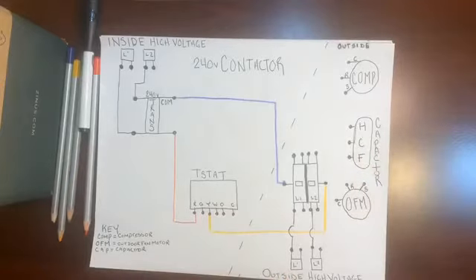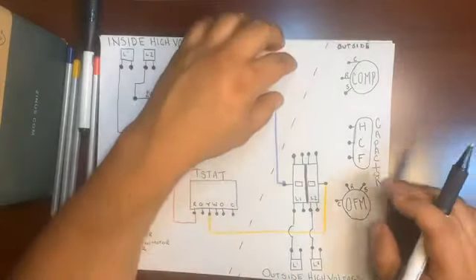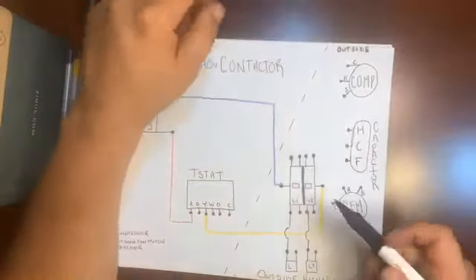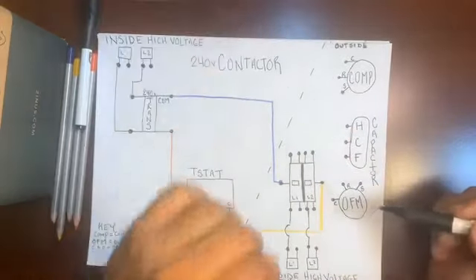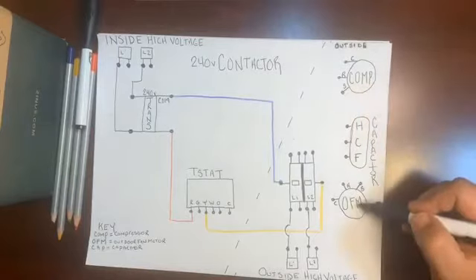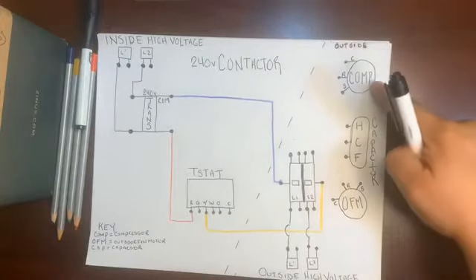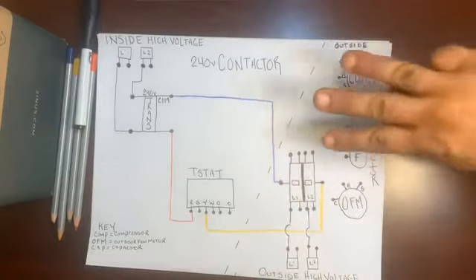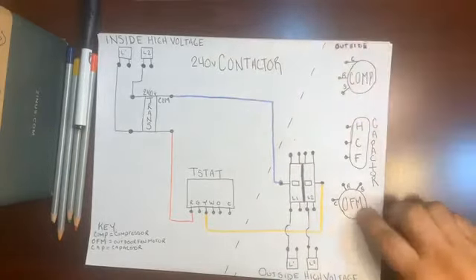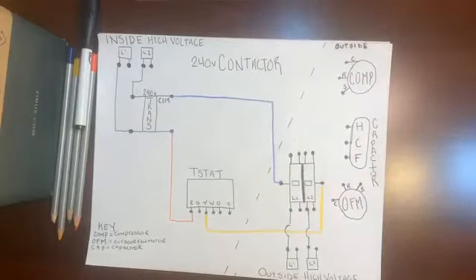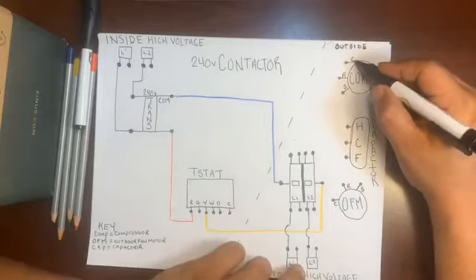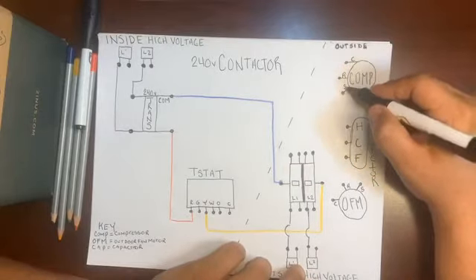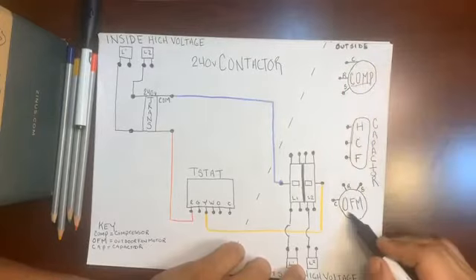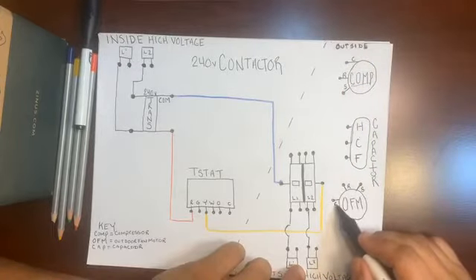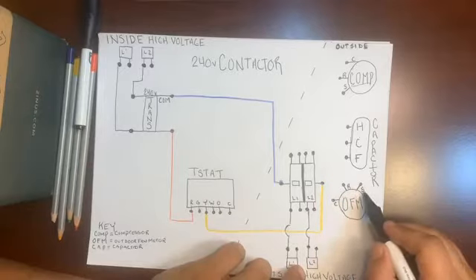Okay, so now this is where we're going to get a little bit more into the condenser. But now that we're here with the contactor, we need to figure out how the high voltage connects. So let's start with talking about the compressor and the outdoor fan motor. Each compressor and each outdoor fan motor that's OEM is going to have 3 wires on it. 3 wires come out of the compressor, 3 wires come out of the fan motor. So if we look at the wires, we're going to see a C for common, R for run, and S for start, and that's on the compressor. We'll look down at the outdoor fan motor, same notion. C for common, R for run, and S for start.